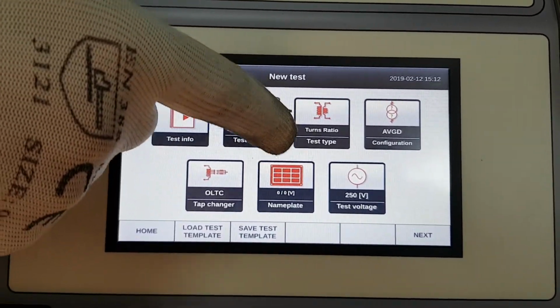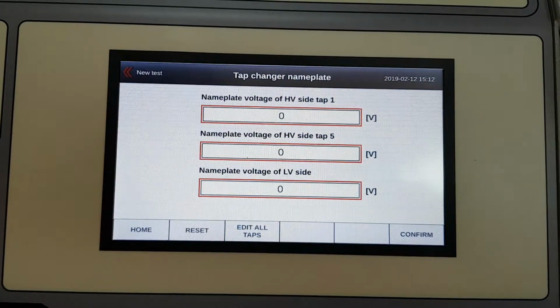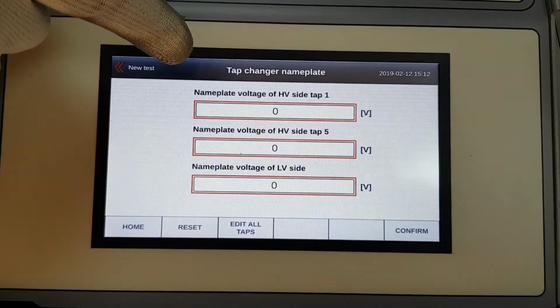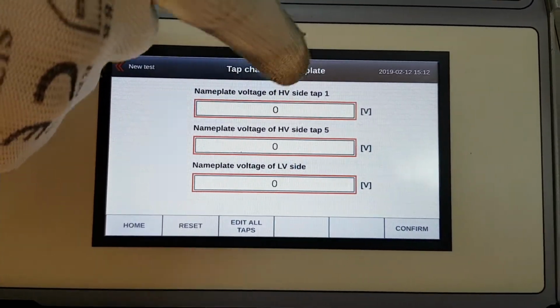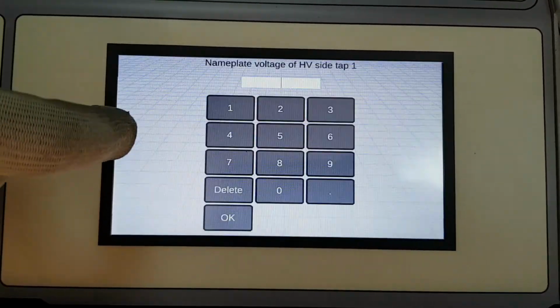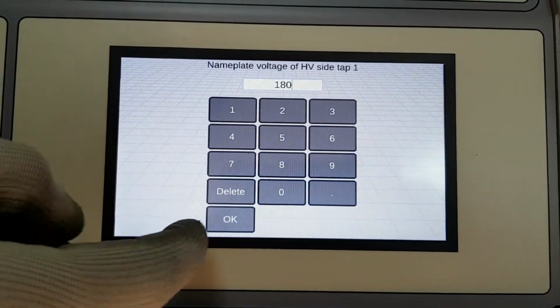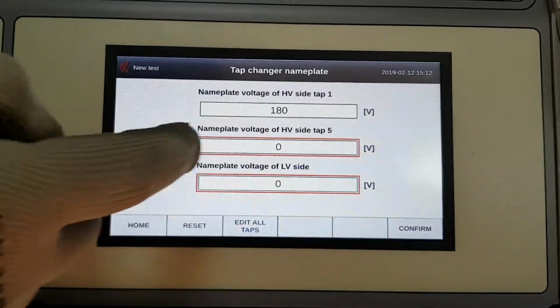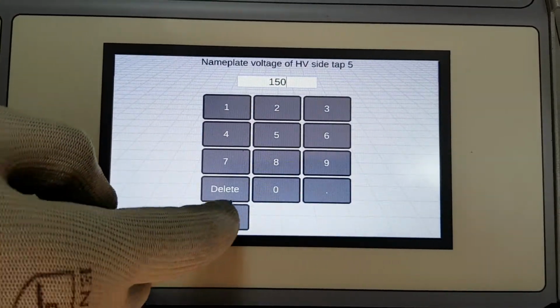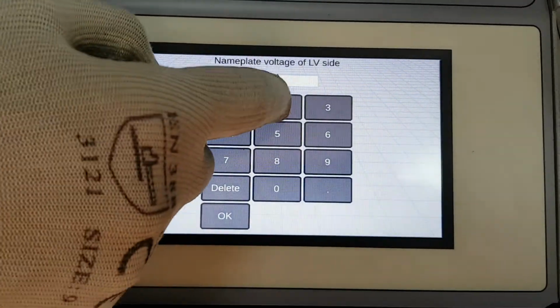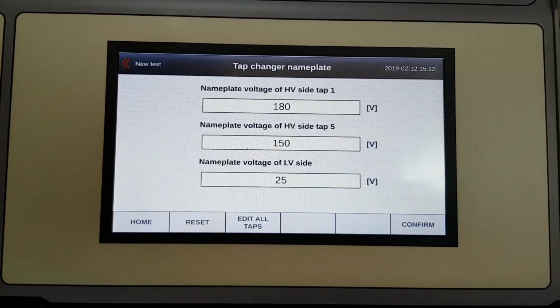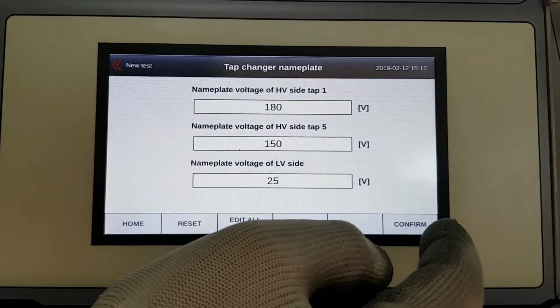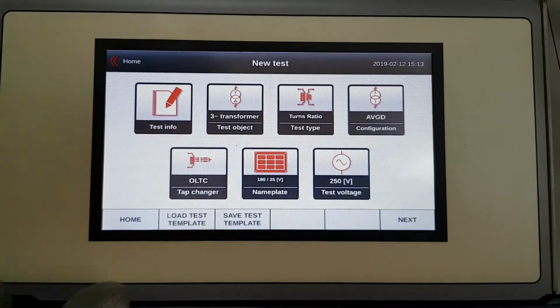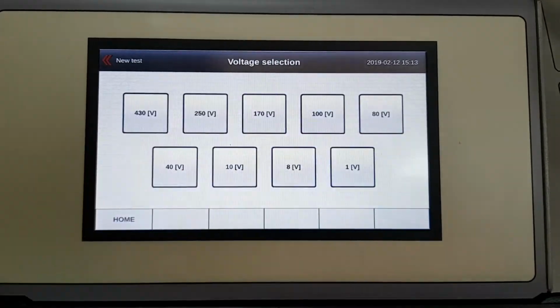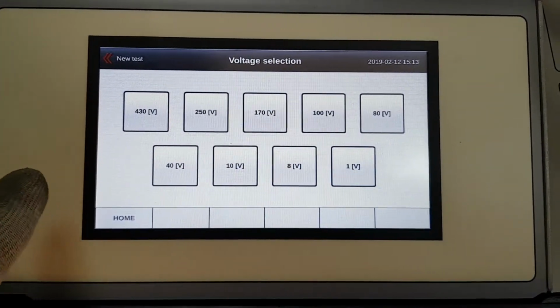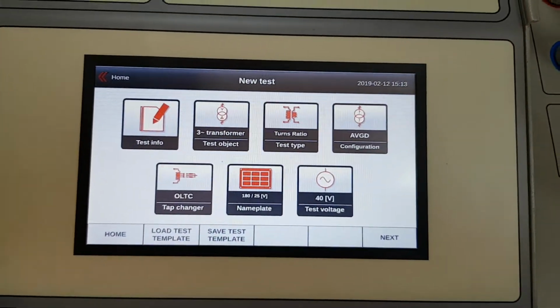Optionally we can input the nameplate voltages of the transformer, so we need to input the nameplate voltage of first tap, last tap, and on the low voltage side. So for the first tap in our case it's 180 volts, for tap 5 is 150 volts, and for the low voltage side it's 25 volts. And I'm going to click the confirm. And the last parameter we need to set is the test voltage. Because this is a small transformer, I'm going to select 40 volts.